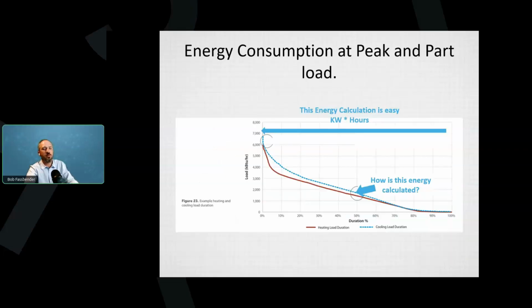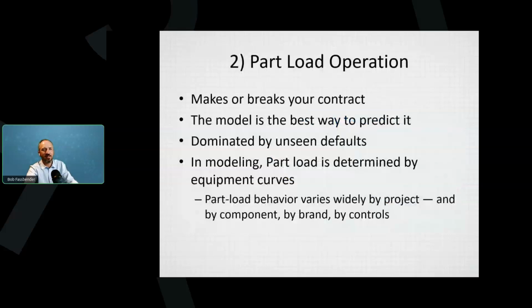So the next thing to understand here, we just talked about the peaks, is so the energy calculation is really easy if you have a constant volume maximum unit. It's just the kilowatts times the hours. The real question is, how does the model calculate the energy in the middle, in the other 99% of the hours? The reason is that part load operation, it will make or break your contract. The model is the best way to mathematically predict it, and it's dominated by unseen defaults. And in fact, most modelers probably go 10 years before they really start to change any of these things.